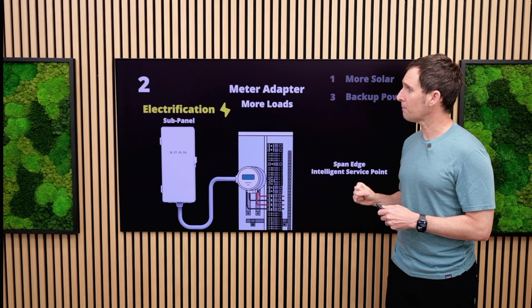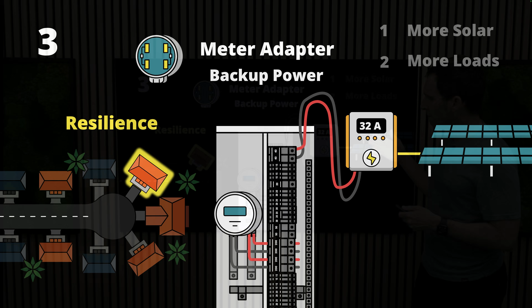Okay, so we talked about adding loads. Let's talk about the third one, which is also super exciting. It doesn't necessarily allow you to avoid a main panel upgrade, but it does allow you to avoid substantial electrical costs. So when we talk about keeping the lights on, if you think about a solar system that's feeding a main panel, you'll notice that if the grid were to go down, turn off, the solar system in and of itself would also turn off.